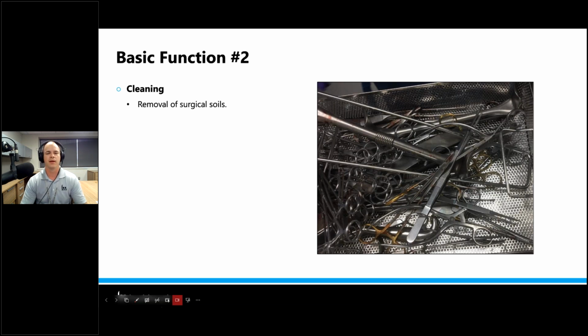And then over here, there's pump number 1 and pump number 2. So in this circumstance, we're talking about soil removal from within lumens. This particular sonic can hook up a lot of lumen instruments and flush them out and clean them out. In this case, it uses 2 different pumps. One pump is for the left side and one pump is for the right side. So if you had any trouble with a lumen cleaning function in this sonic, it may be one pump while the other pump is fine, right? That's where I'm going with this: understanding some of those basics will help you understand how to troubleshoot if you ever run into a problem.